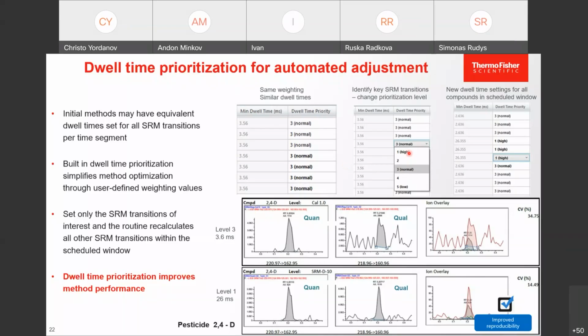When we set this to high, we change the dwell time, the amount of time which is required to acquire this transition. So the badly performing transitions have a higher dwell time, more milliseconds, while the other transitions are automatically recalculated. So the better performing compounds have lower dwell time, and badly performing transitions have a higher dwell time.